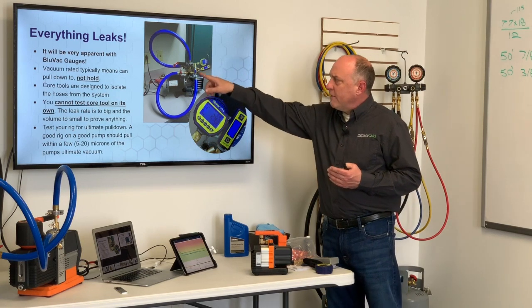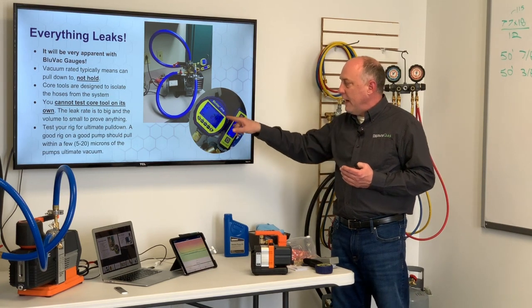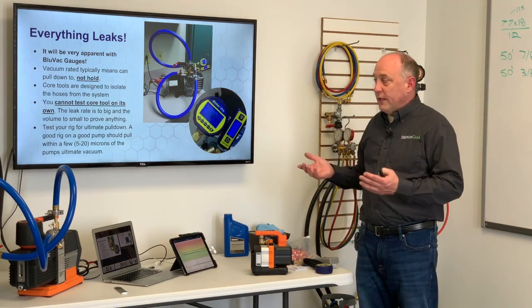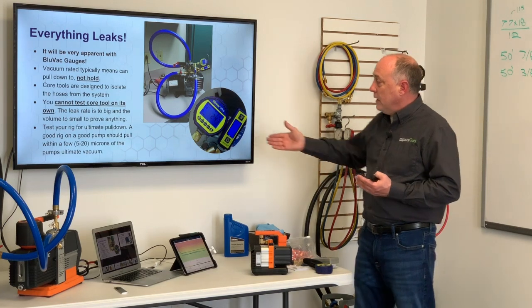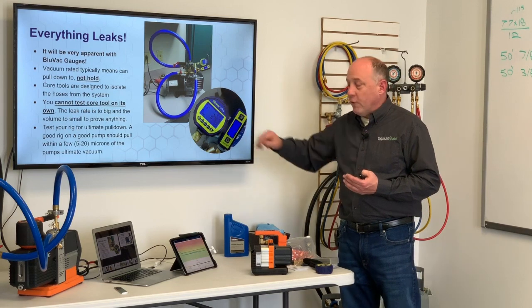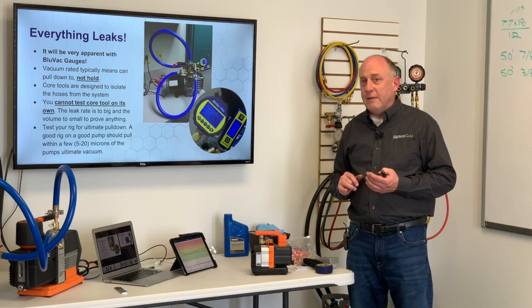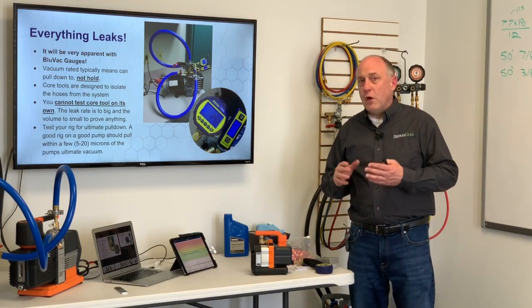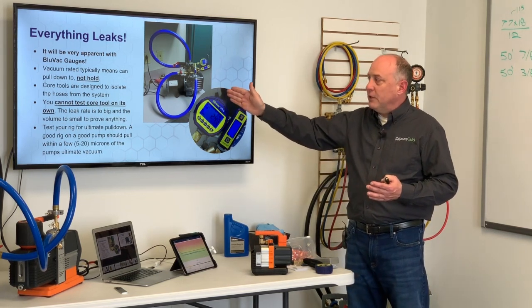Here I've got this pump running, and I pulled down to 19 microns at the pump and 24 microns at the hose — a 5 micron difference in pressure between those two. Part of that is moisture in the hose that's still boiling off; it could be microscopic leaks in the hose. But I can have 24 microns at my hose end. If you did this with an Appion hose, you might get down to 75 to 100 microns max. If you did this with a quarter-inch hose, you might get down to 400 microns at the deepest amount of vacuum.